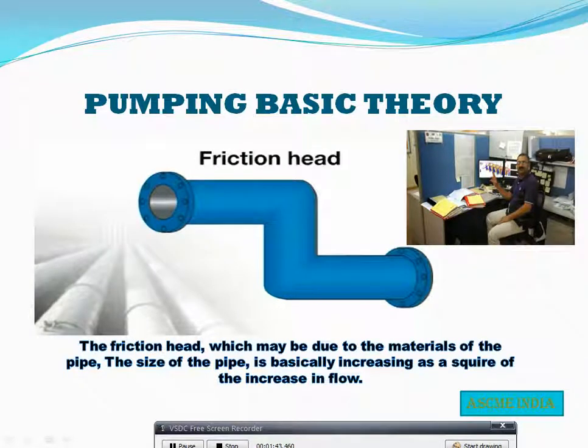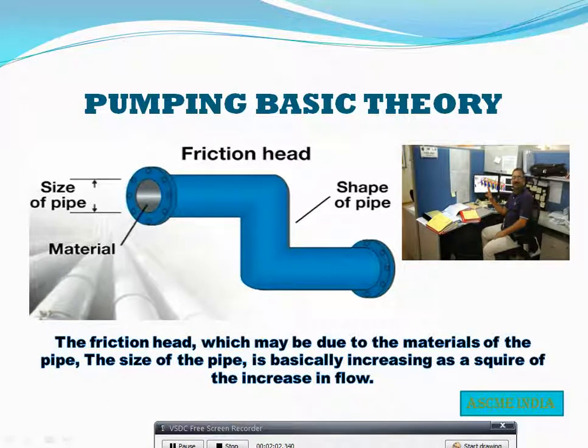Friction head: the friction head, which may be due to the material of the pipe and the size of the pipe, is basically increasing as a square of the increase in the flow.